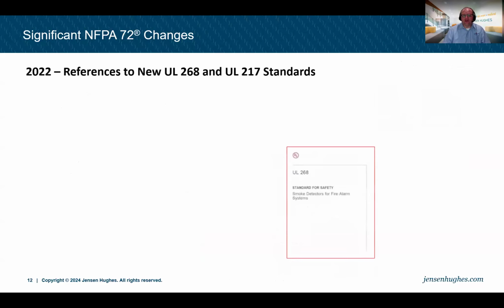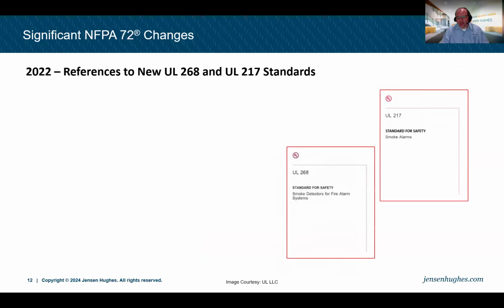Now, a couple of significant changes have been made to our smoke detection over the last few years. Really, all smoke detectors and smoke alarms are listed to Underwriters Laboratories or ANSI standards, specifically UL 268 and 217. 217 is for smoke alarms, those single station alarms that you might have in your own home, as an example. And UL 268 is for smoke detectors that are connected to a fire alarm control unit.